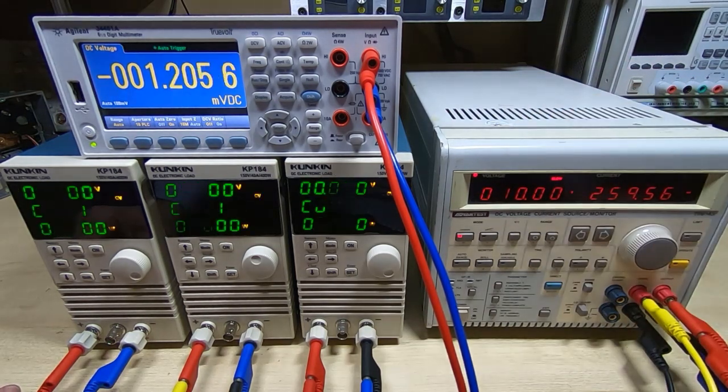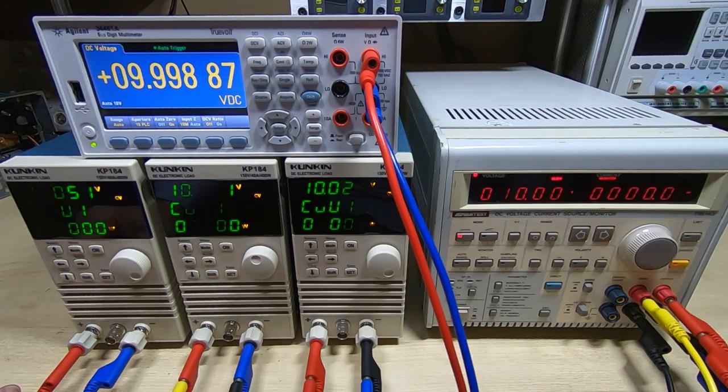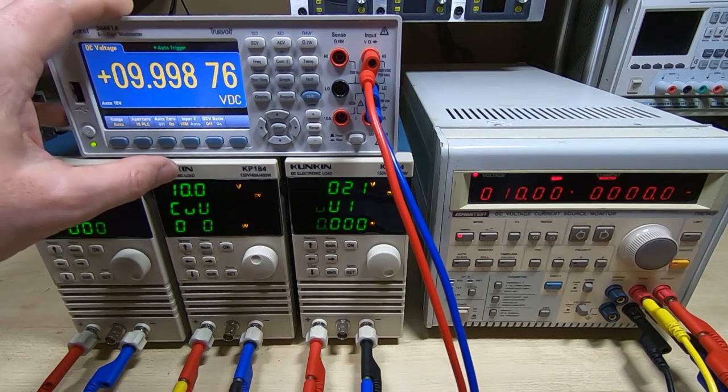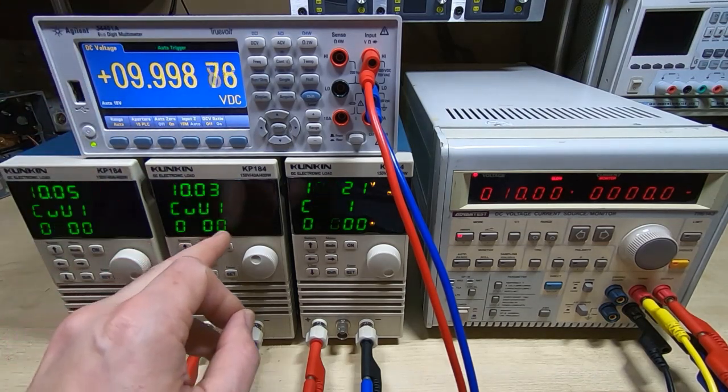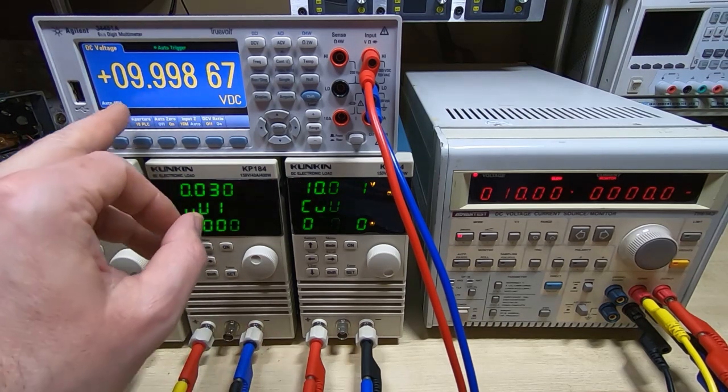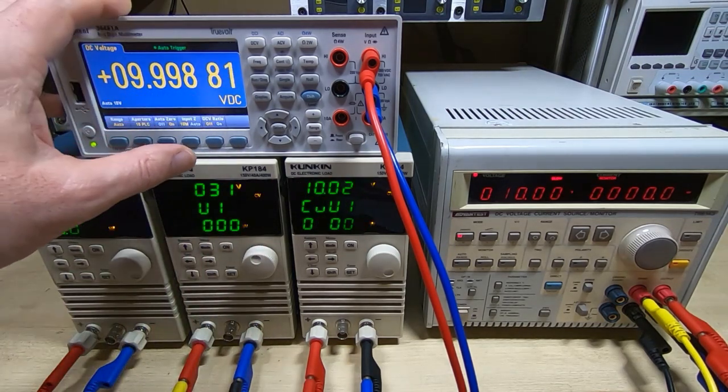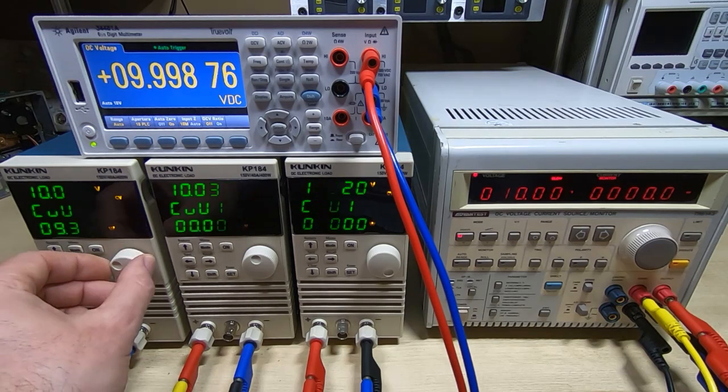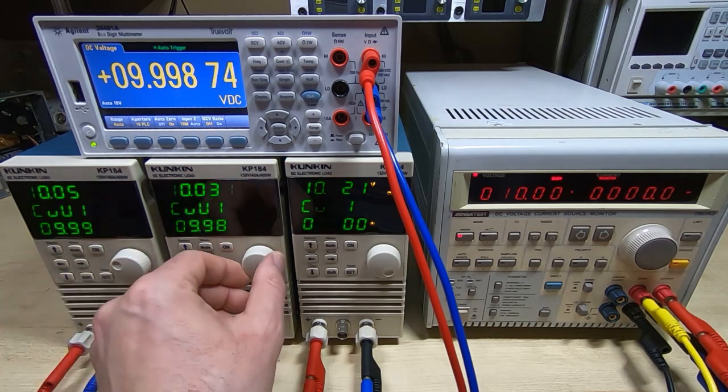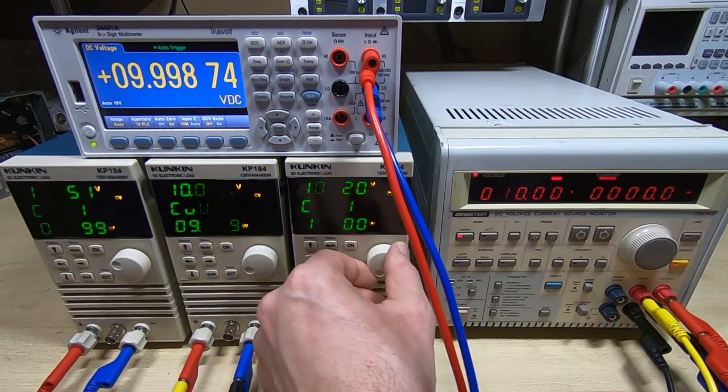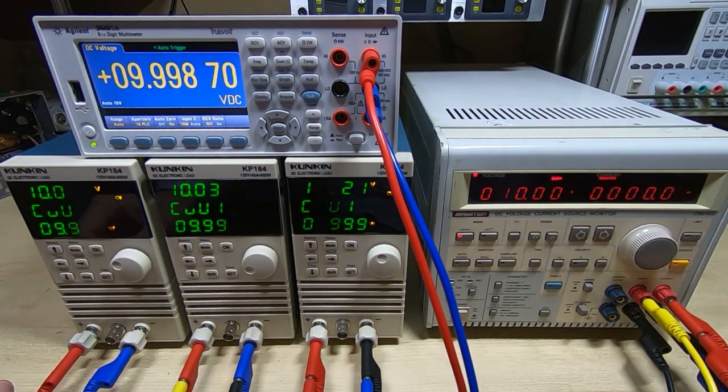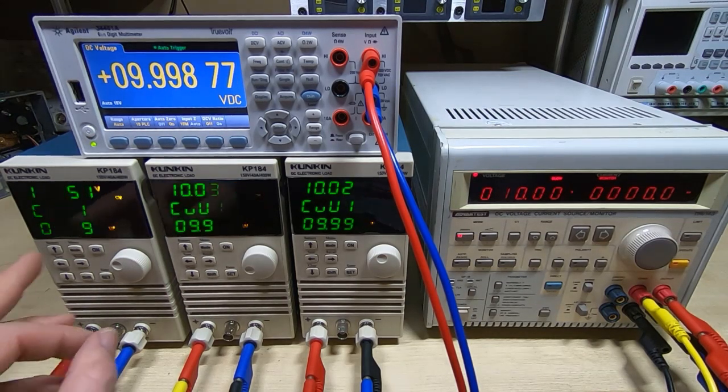We'll set 10 volts on the source, switch it on, and we can see we're getting the readings in the top line of the KP184 and very close to 10 volts. What we have to do is dial in on the bottom line of the KP184 the value we're actually measuring from our reference. So in this case it's 9.9998. What I've done is set them all to read as closely as I can the value that's shown on the Agilent. What you then do is press the set key.